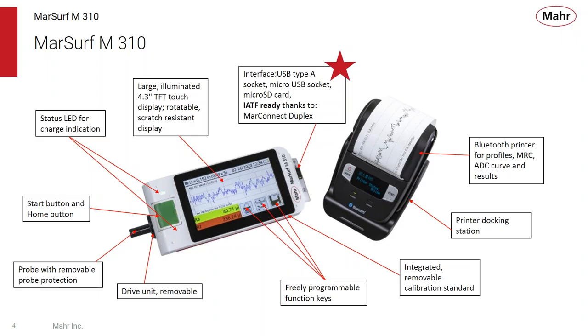Going clockwise around the picture, we have the same large 4.3-inch touchscreen display, which you can rotate. It's a glass display, so it's very scratch resistant. The M310 has two LEDs for giving an indication of charging and when it's operating. It has a hard plastic start-stop button that's meant to be used a lot on the shop floor. It has a removable probe just like the PS10 and also comes with a probe protection device. The drive is removable, so you can mount that into stands or put it into special applications. You have 3 freely programmable function keys, which you can assign to saving data, setting tolerance, etc.